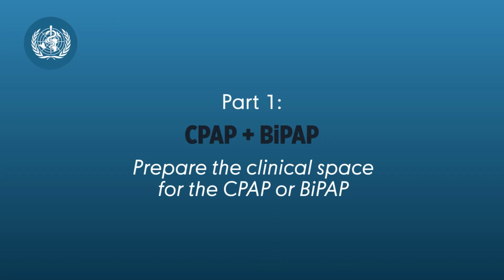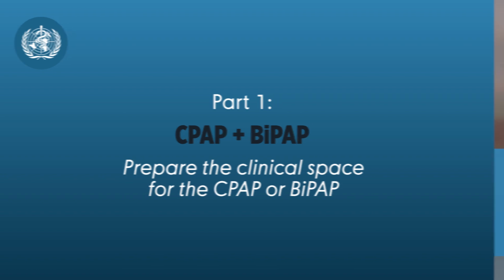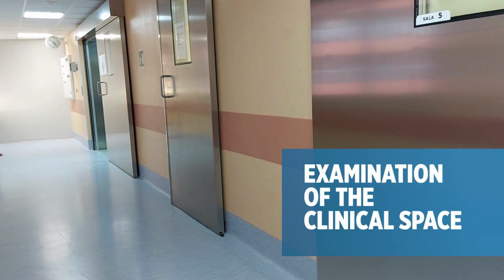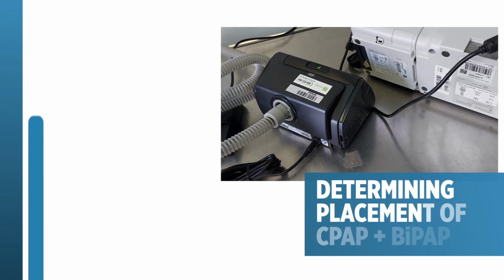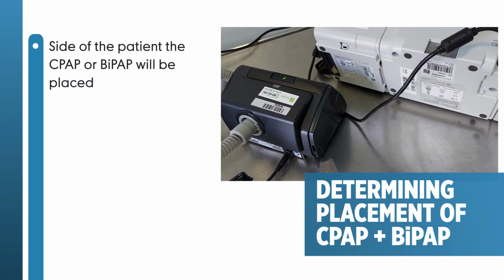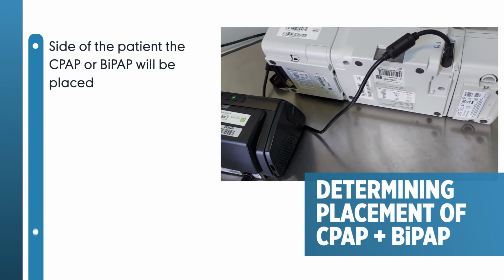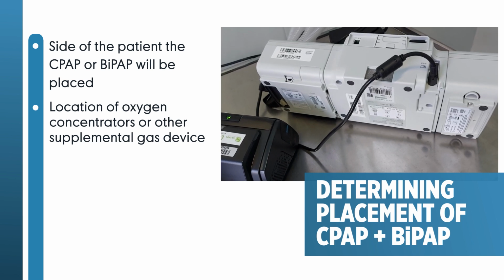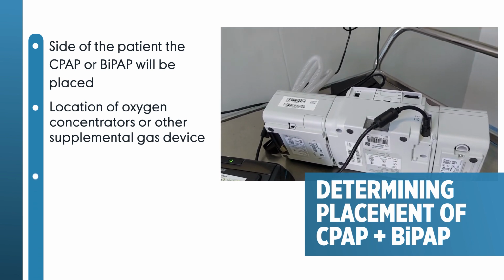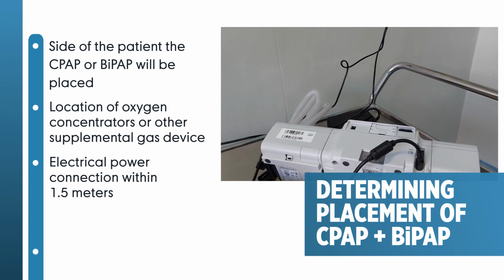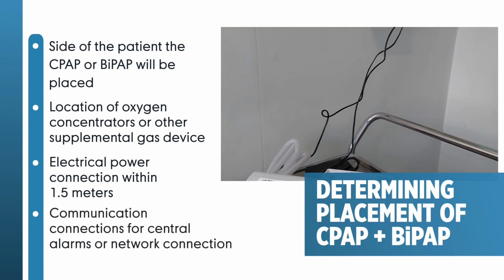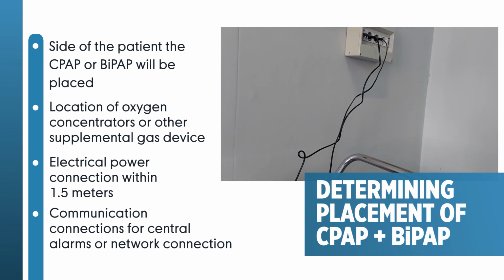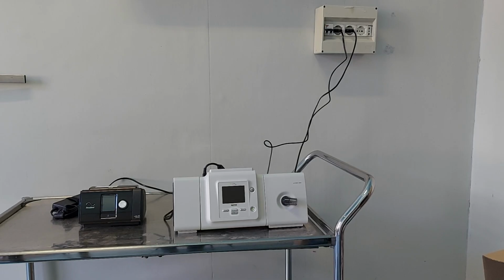Before your new CPAP or BiPAP arrives, it is important to confirm that the clinical space it will be used in is ready for it. Several aspects of the clinical space will need to be examined. Determine where the device will be used in the clinical ward. This would include on which side of the patient the CPAP or BiPAP will be placed, location of oxygen concentrators or other supplemental gas device, electrical power connection within 1.5 meters, and any communication connections for central alarms or network connection. If the device is portable and contains a rechargeable battery, when deployed, it should be stored in a location with outlets for electrical charging.